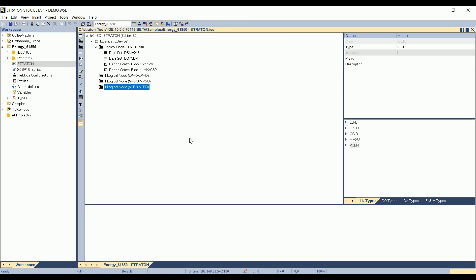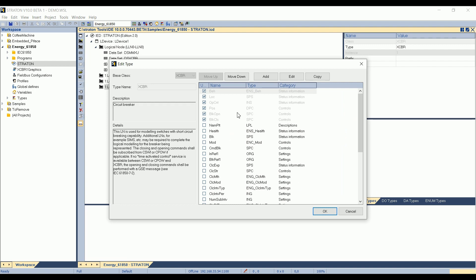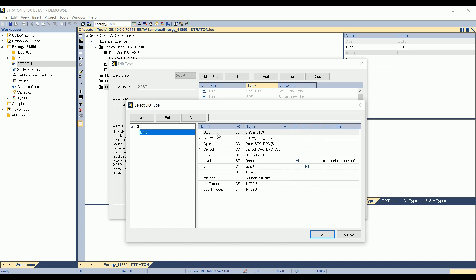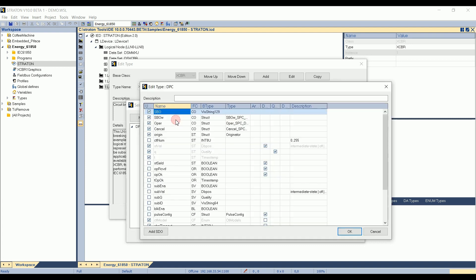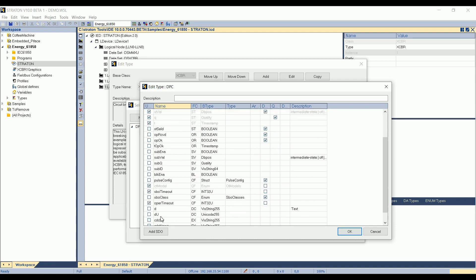For the circuit breaker node, if we edit the type, here at the bottom right, logical node types, I expand XCBR, right-click on it, edit type. I can see that we have the data object position for the circuit breaker with the command data class double point controllable. If I double-click on the command data class, I can see that data objects are here. And if I click on the edit button, I can see that here grayed are the mandatory data objects, and we have also optional data objects which have been checked: select before operate, operate, cancel, and other data objects.